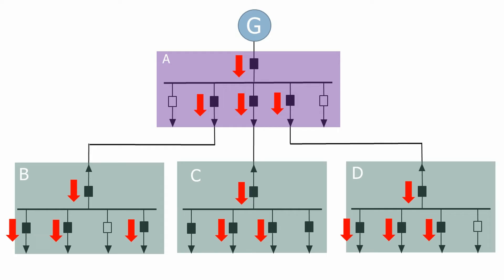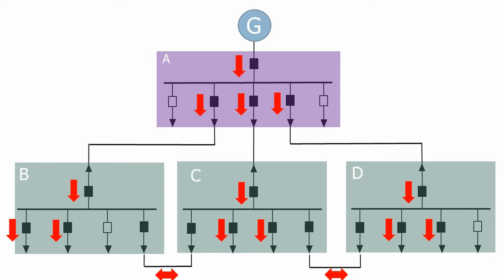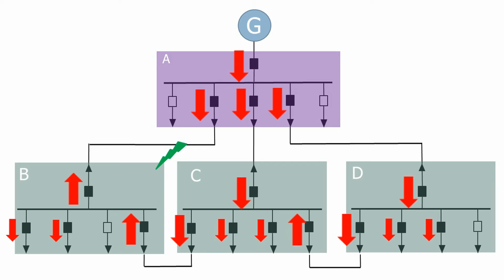To achieve this goal, we provide additional interconnectors between the substations. These allow power flow in either direction, which provides flexibility and allows load currents to be shared evenly. This is normally called a solid or solidly connected system. When we apply our feeder fault, the currents increase in both the generator and the source substation, but this time some currents change direction and we back-feed the fault from Substations B, C, and D.